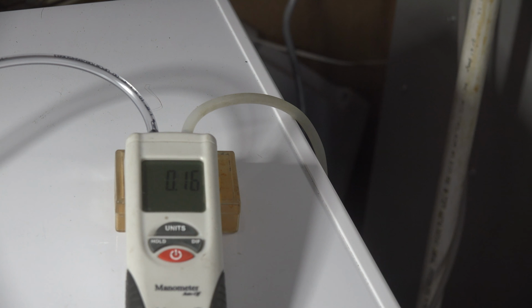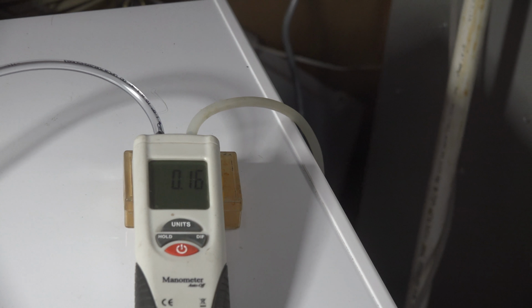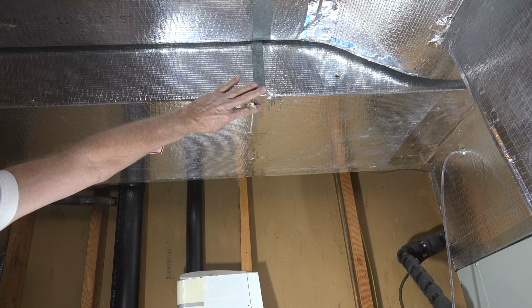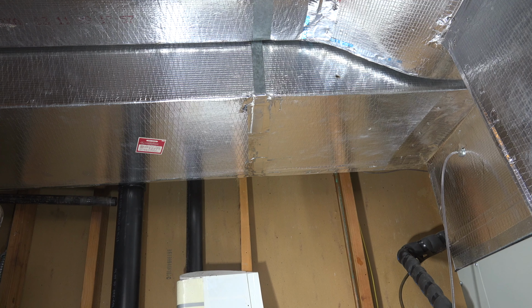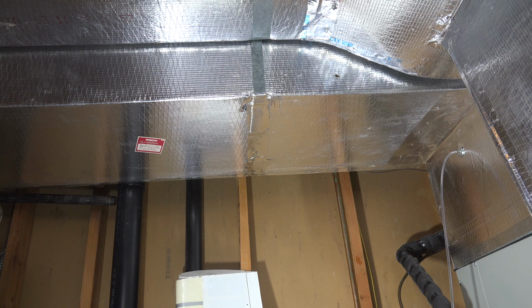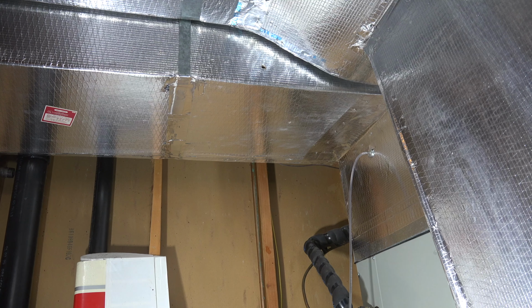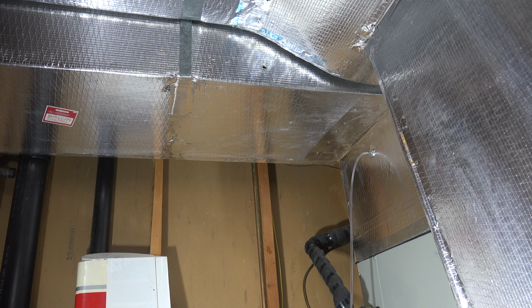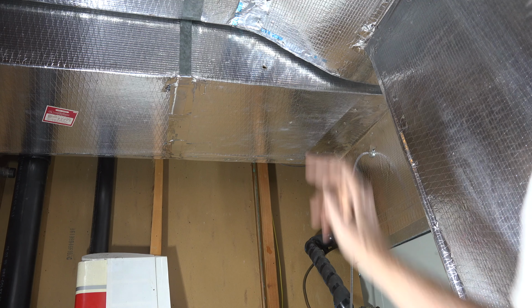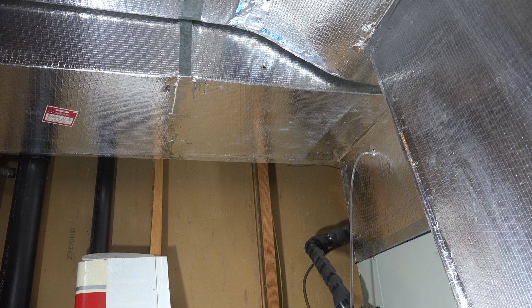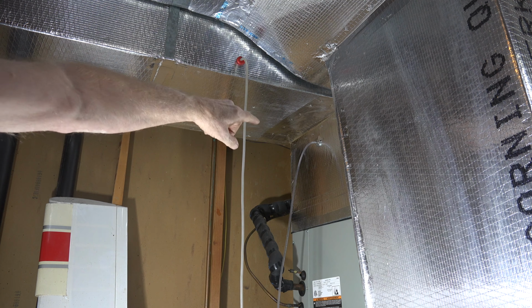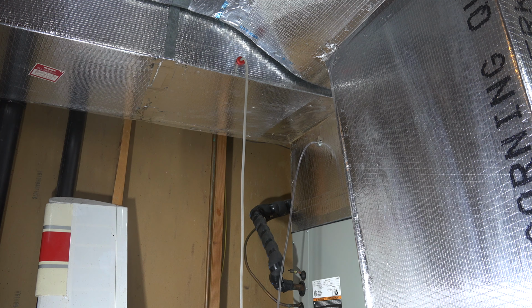The next thing I want to test is the pressure drop across the supply air. Now this is one of the supplies. There's two supplies in this thing. So really all I'm going to check here is, if you look closer, you can see I've got the probe over there on the right on one side of that T, and I'm going to just check across that T to see if there's any restriction there. And if you notice on the upper part of the picture, there is a hole right there, and I'll put the probe in there and we'll see if there's any difference across there. Now you can see I have the two probes in there, one of them downstream of the air conditioning coil and one of them right after the T. So let's see if we have any pressure drop across that T.